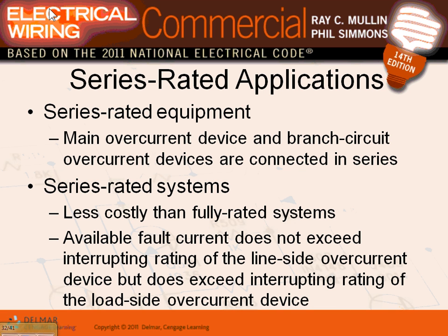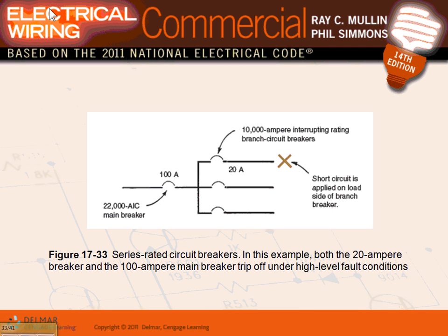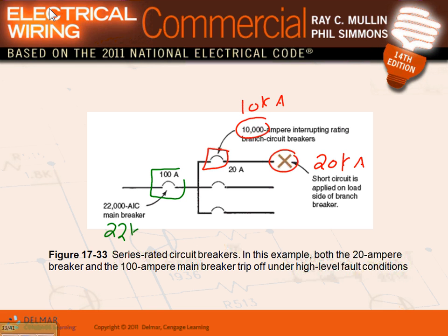Okay, series rated systems. I'll show you guys an example, right here. Series rated system, and we talked about this many, many times. So if the short circuit's right in here, say my short circuit, let's just say, throw a value here, is 20 kiloamp. The rating of this equipment is 10 kiloamp, this device right here. The rating of the main is 22 kiloamp.